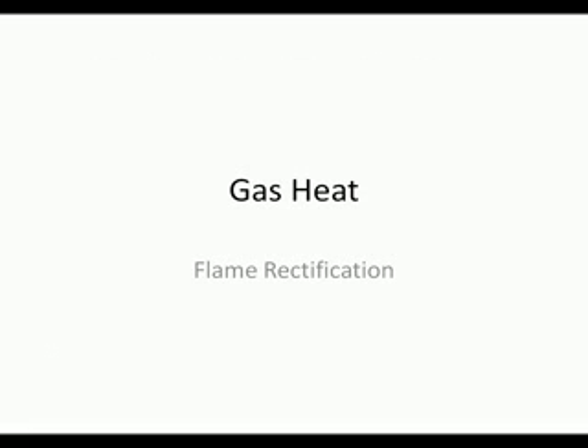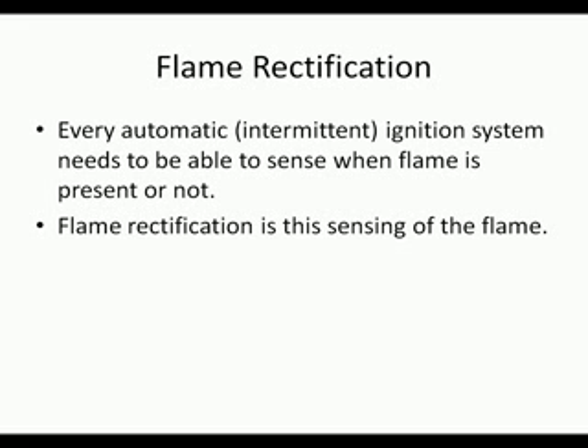Problems with the electronic ignition or flame rectification are almost always due to a poor ground. Make sure you run a ground wire from the burner to the equipment frame to the pilot burner to the control module before replacing the control. Often a poor ground is the cause of intermittent flame failures.